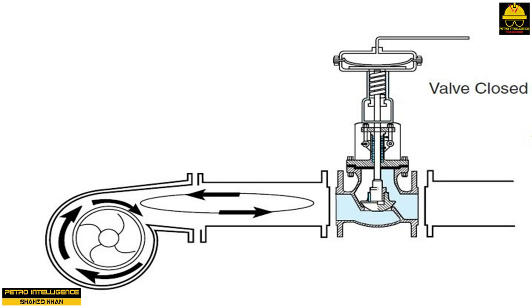This principle can be illustrated by following the path of liquid as it enters a centrifugal pump with an open discharge valve. As fluid moves from the suction inlet into the impeller, flow is accelerated into a discharge chute known as a volute. The volute is a specially designed chamber that widens within the pump. Shutting the discharge valve stops flow to the process unit, but circulation within the pump continues. As the impeller turns, fluid is accelerated into the large volute discharge. Circular motion, clockwise, is sustained in the volute and discharge pipe up to the discharge valve, as shown in the picture.